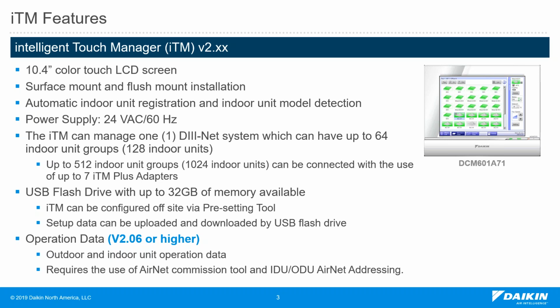iTouch Manager can manage one D3net system, which is 64 group addresses, or when we add the ITM plus adapter, we can go up to 512 group addresses or 1,024 indoor units. We can add 7 ITM plus adapters to the ITM. You can use a USB flash drive in multiple locations with the ITM presetting tool, to upload or download data to the ITM. It is also used when you're doing a software update to the ITM.